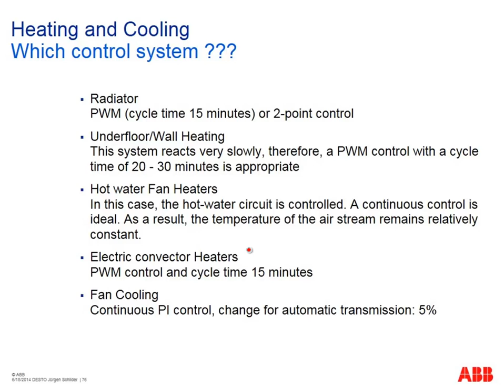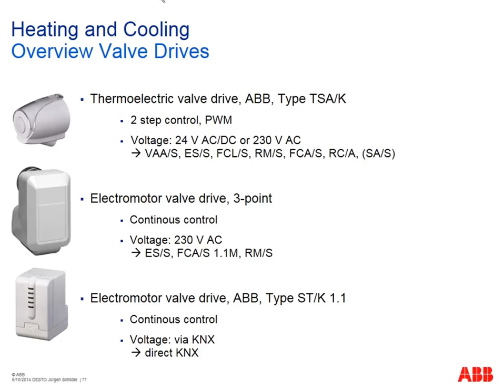Summary of the different valve drives we can operate, which are normally on the market. Electrothermal valve drives, as already mentioned. We have some components, typically 2-step controller or pulse width modulation. 24 volt or 230 volt valve drives are available. Then these electromotor valve drives. This one is an ABB product here, this electrothermal valve drive, but this one is not. It's a motor valve drive, not KNX, where we need a dedicated component like the electronic actuator or the fan coil actuator to operate this. But continuous control, or you use the STK directly, a direct KNX controlled motor valve drive.